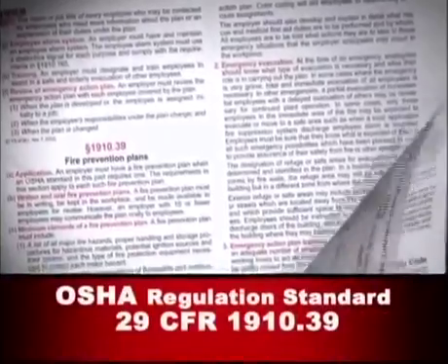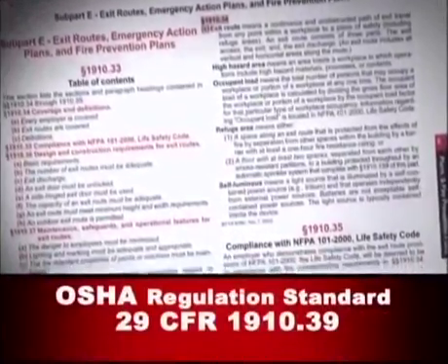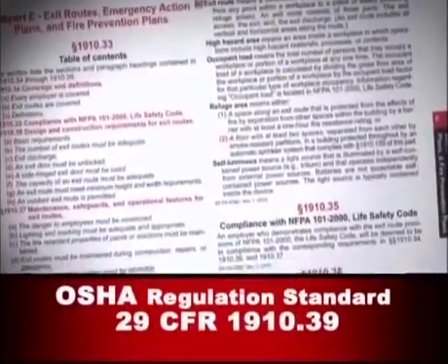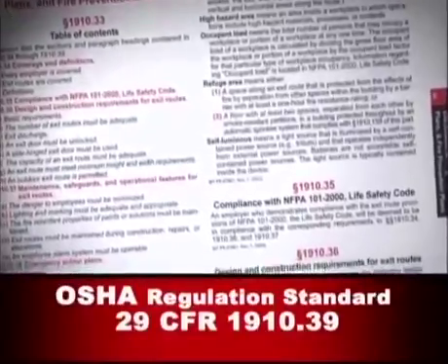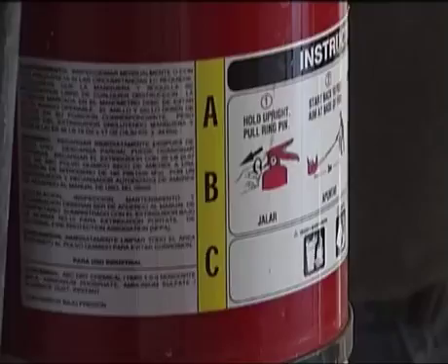Although employers are only required to have a fire prevention plan when the applicable OSHA standard requires it, OSHA strongly recommends that all employers have a fire prevention plan. Guidelines for a fire protection plan are found in OSHA 29 CFR 1910.39. This plan must be made available to all employees in writing if there are 11 or more people employed at your workplace.